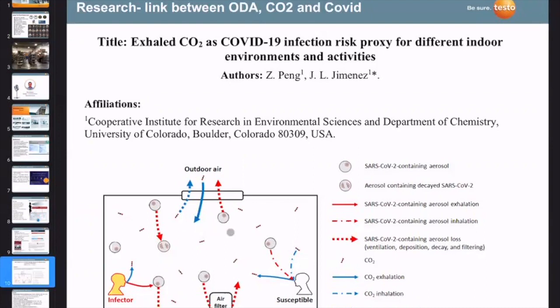So that's the reason why today ASHRAE states that the CO2 levels must be monitored and documented consistently in all schools, all classrooms that are occupied, to determine what the relationship is between that and potential infection of COVID-19. Because point of fact, the three things that we all exhale on a daily basis, well, I mean, if you're infected, but it's water vapor, it's CO2, and it's the viral particles inside the water vapor droplets.